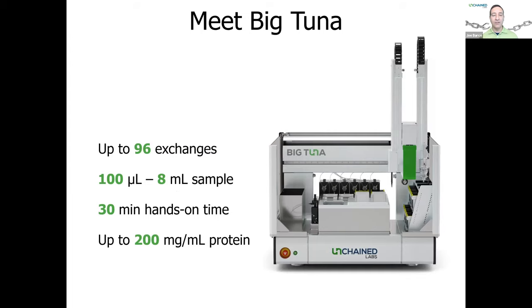Big Tuna will allow you to do up to 96 simultaneous buffer exchanges. You can work at low volumes — as low as 100 microliters of sample — up to as much as 8 mils per well. You can use multiple wells for a single protein. Setup time is less than 30 minutes to get your experiment designed, prepare your deck, and then leave. It works with a wide variety of protein concentrations, from sub 1 mg/mL all the way up to about 200 mg/mL of IgG.